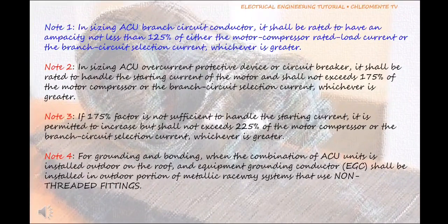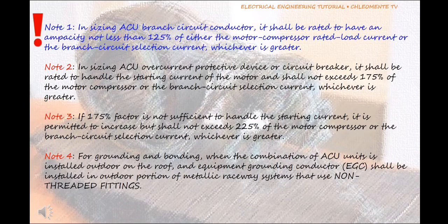Note 1: In sizing ACU branch circuit conductor, it shall be rated to have an ampacity not less than 125% of either the motor compressor rated load current or the branch circuit selection current, whichever is greater. Note 2: In sizing ACU overcurrent protective device or circuit breaker, it shall be rated to handle the starting current of the motor and shall not exceed 175% of the motor compressor or the branch circuit selection current, whichever is greater.